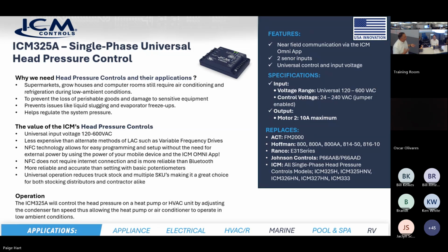So with the 325A, we made it universal. We took all that guesswork out. Can't tell you how many calls I used to get. We used to have a 326 versus a 325, and the 326 was for refrigeration units, so everything had to be line voltage. The 325A was for supermarkets and things like cell towers, they had 24 volts available.